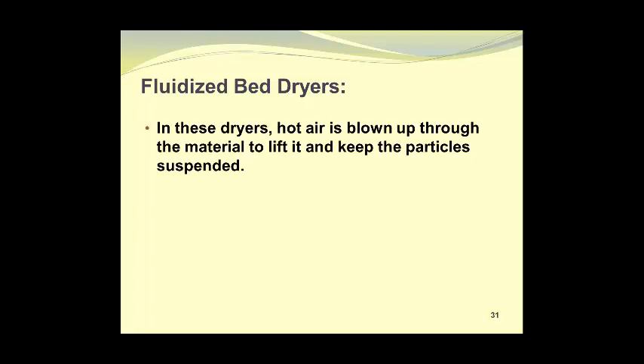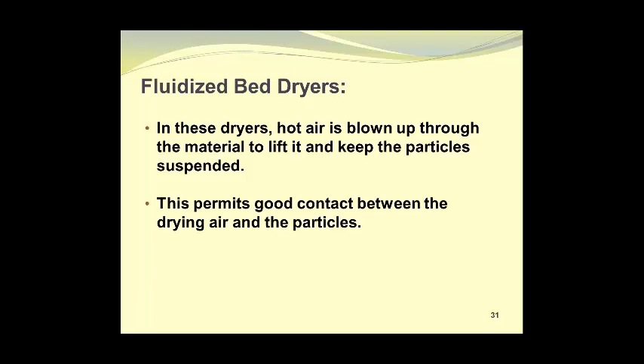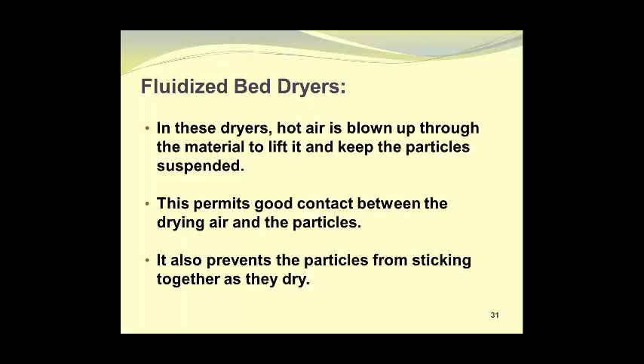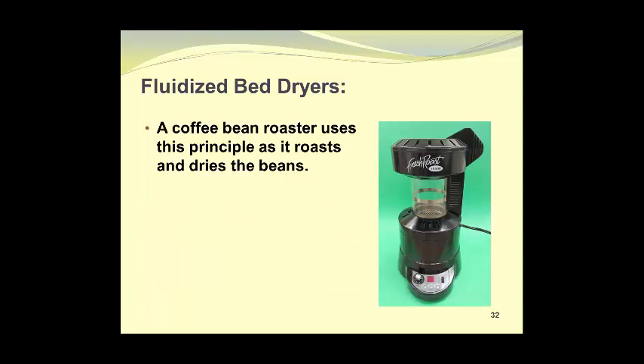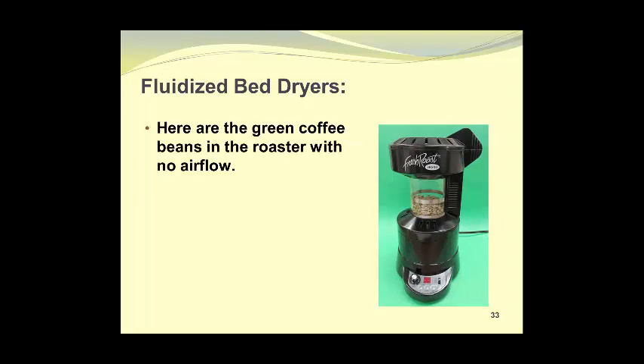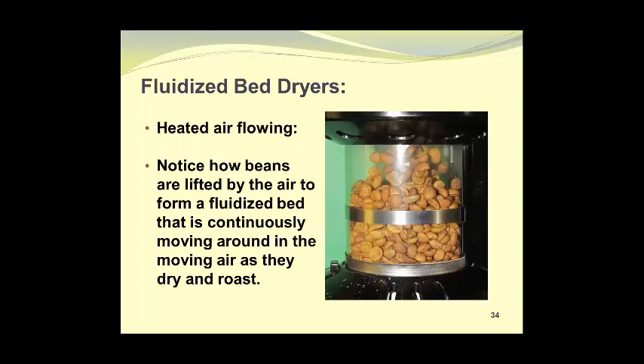Fluidized bed dryers are quite interesting. In these dryers hot air is blown up through the material to lift it and keep the particles suspended in the drying air. This permits good contact between the drying air and the particles, and also prevents the particles from sticking together as they dry. A coffee bean roaster uses this principle as it roasts and dries the beans. With no air flow the beans rest on the bottom of the drying chamber. When hot air is flowing, the beans are lifted by the air to form a fluidized bed that is continuously moving around as they dry and roast.